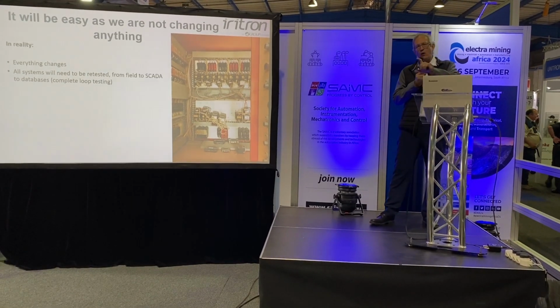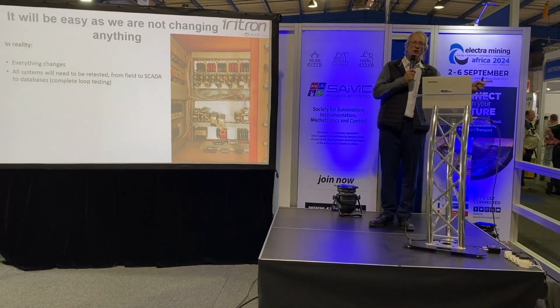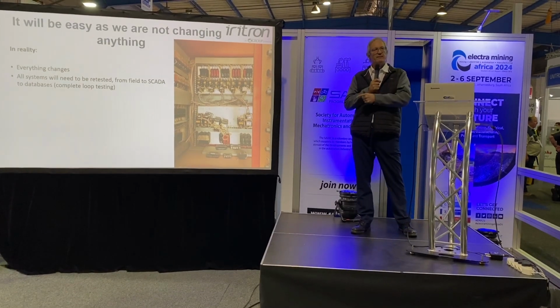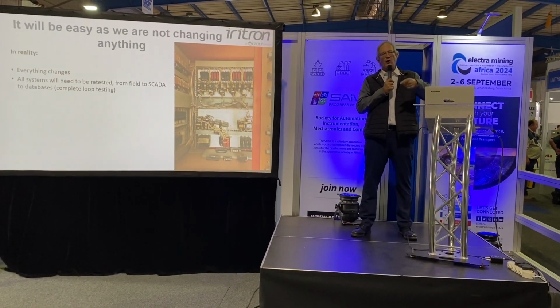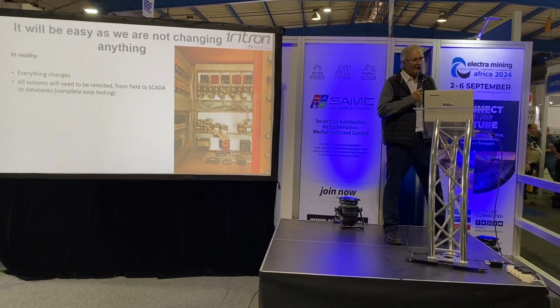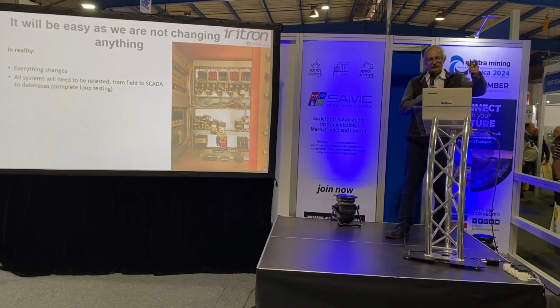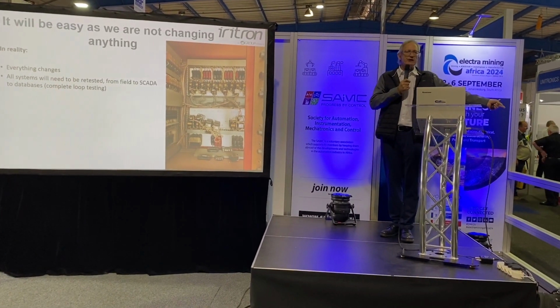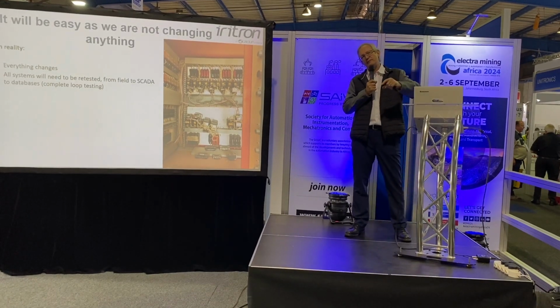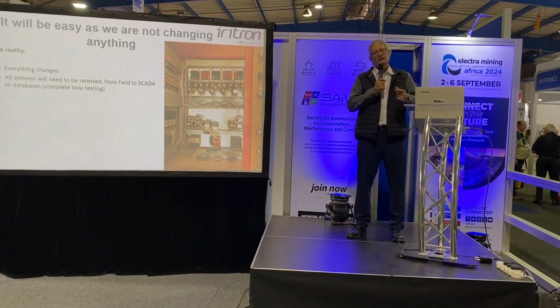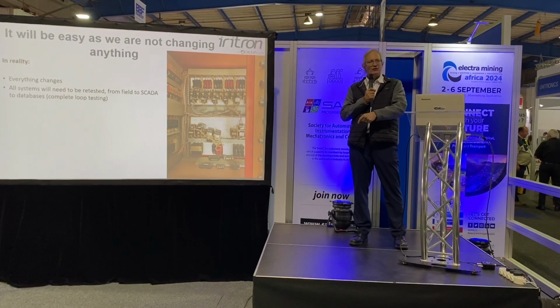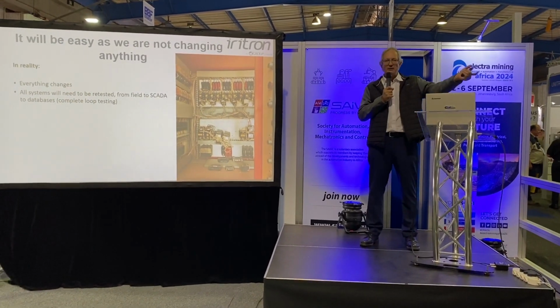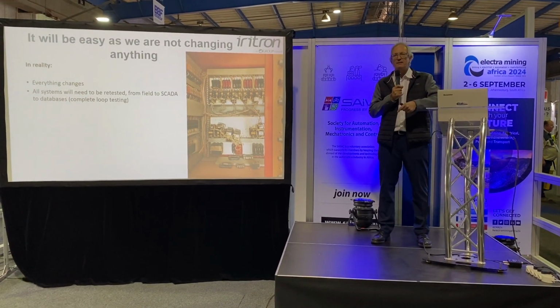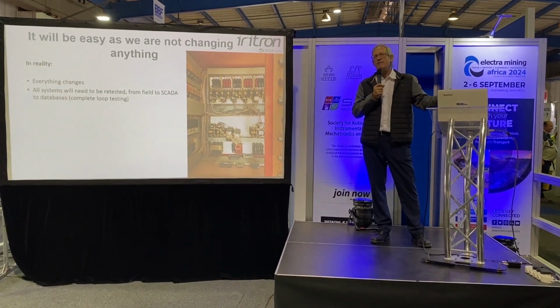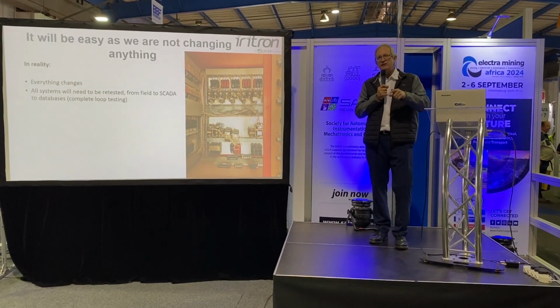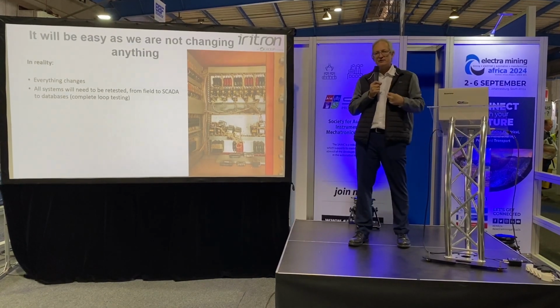Because if you're ripping out one part of the control system, you have to retest the whole control system. So from the field, from the actual instrumentation, through the wiring, to your PLC panel, to your MCC, to your SCADA, and to your databases that live on the SCADA, you have to loop check everything, especially if you've changed out PLCs.